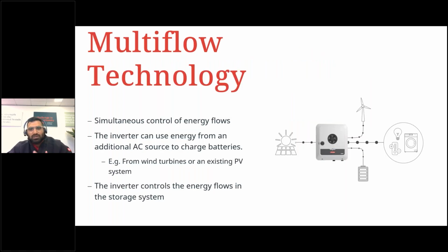Well, as we discussed earlier, we can charge the battery even in backup mode using Multiflow technology. So let's take a quick look at what else is possible with Multiflow. One of the cool features of Multiflow is that we can charge the battery from other AC sources on site. So this can be a wind turbine or an existing inverter. It could be a third-party inverter. It could be an old Fronius inverter. It doesn't matter. And here the inverter will take the surplus AC power available from this additional AC source and convert it into DC and store it in the battery.